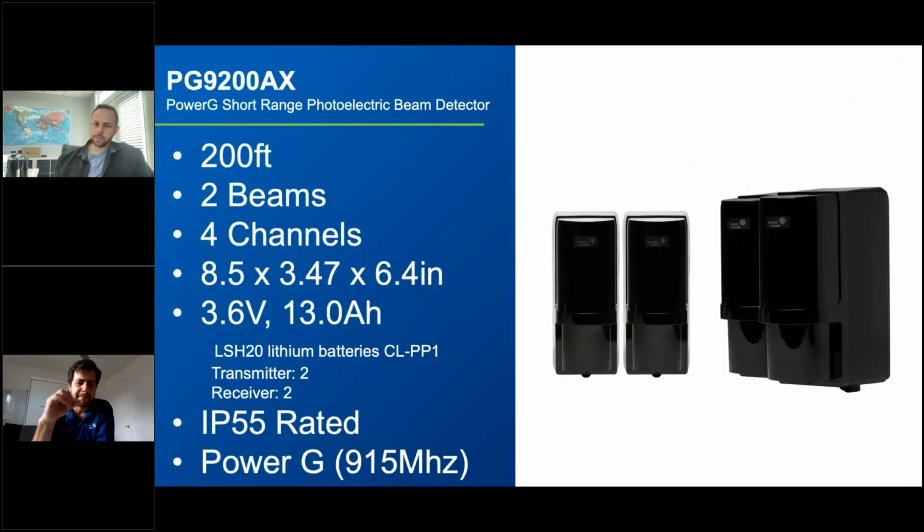So Mark, just to make this clear, the alignment dial is kind of a little aim that you have there, and while the other sensor is on the other side, and you get closer to that, it is kind of a periscope mirror there that you aim at the other sensor. It's really interesting how optics has developed that and it makes the alignment very easy. And from my understanding, it has a two-time magnification also. When you set these up, you start at the transmitter side and then work on the receiving side.